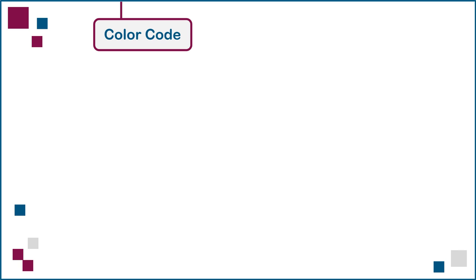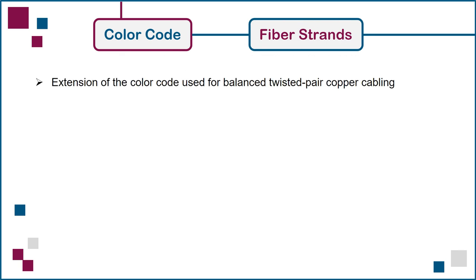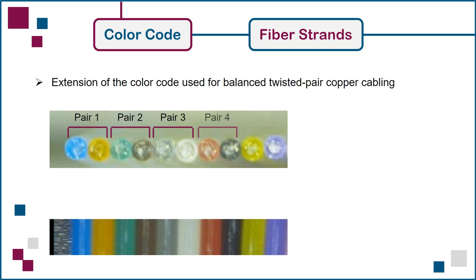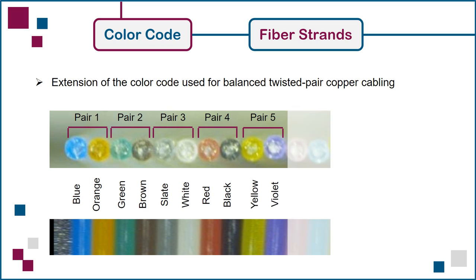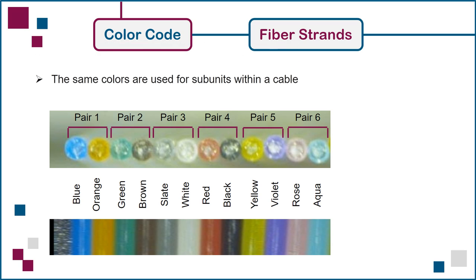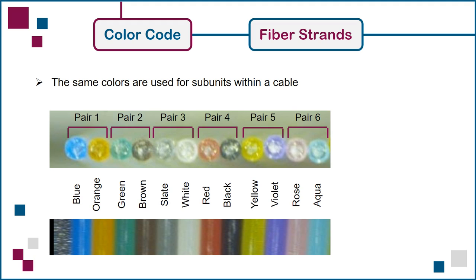The color code used to identify and sequence individual fiber strands is an extension of the color code used for balanced twisted pair copper cabling. The first 5 pairs, or 10 fibers, use the same colors as their copper counterparts, but an additional 2 colors, rose and aqua, were initially required, because fiber cables contained strand counts in multiples of 12, such as 24 fiber and 48 fiber, versus 100 pair and 300 pair copper cables. The same colors are used for subunits within a cable. For example, a 96 fiber loose tube cable may contain 8 buffer tubes, each containing 12 fiber strands. Tube number 1 would be blue, tube number 2 would be orange, and so on. So the same color code identifies both the sequence of the fibers and the sequence of the tubes containing the fibers.